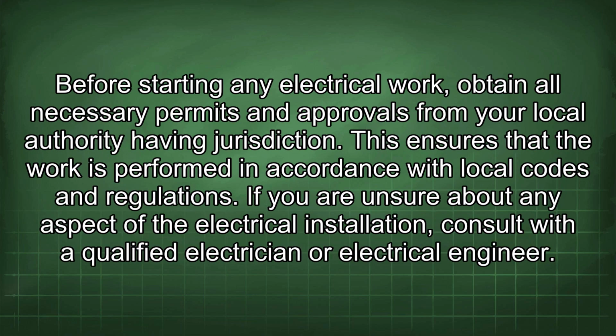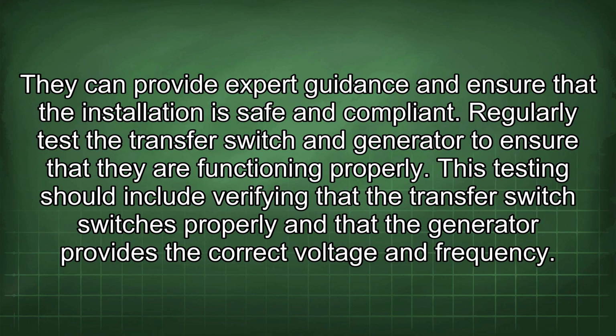Before starting any electrical work, obtain all necessary permits and approvals from your local authority having jurisdiction. This ensures that the work is performed in accordance with local codes and regulations. If you are unsure about any aspect of the electrical installation, consult with a qualified electrician or electrical engineer. They can provide expert guidance and ensure that the installation is safe and compliant. Regularly test the transfer switch and generator to ensure that they are functioning properly. This testing should include verifying that the transfer switch switches properly and that the generator provides the correct voltage and frequency.